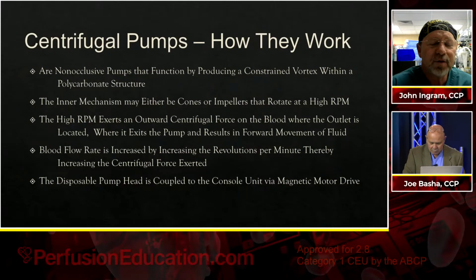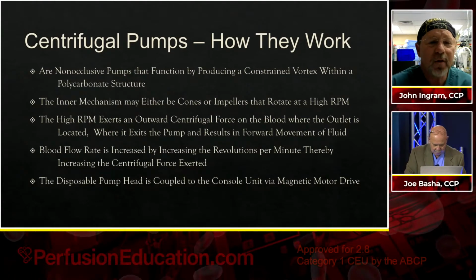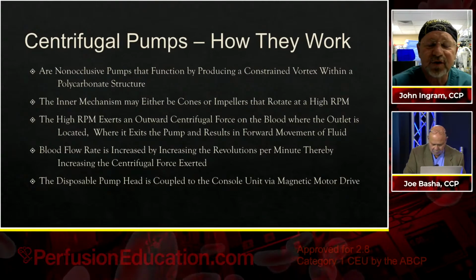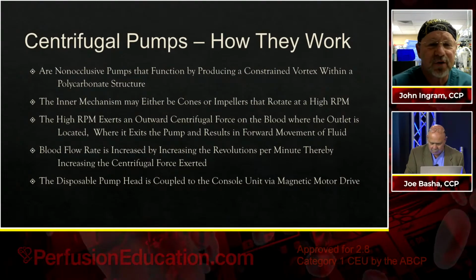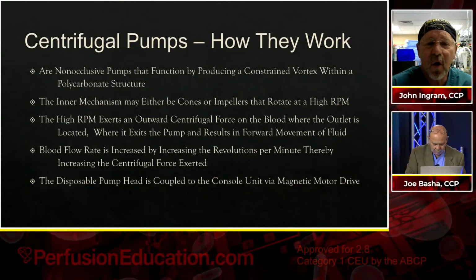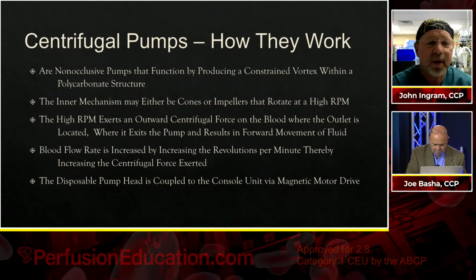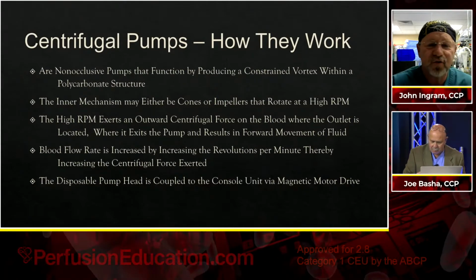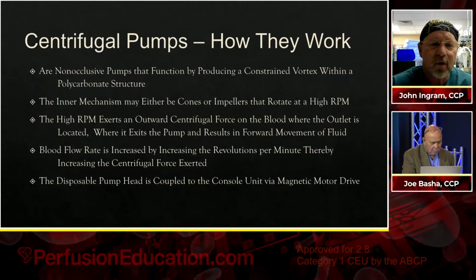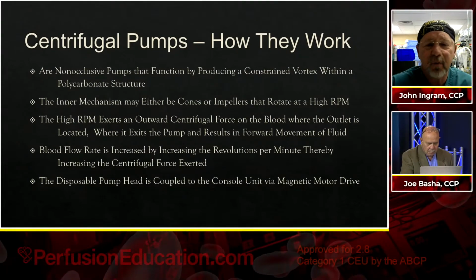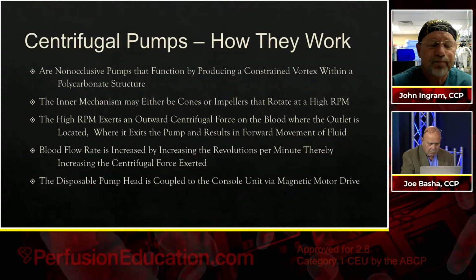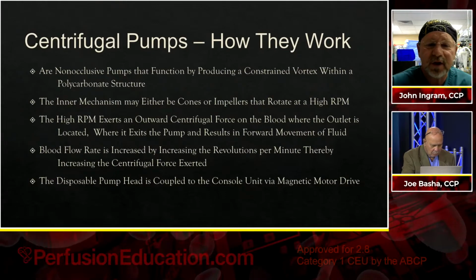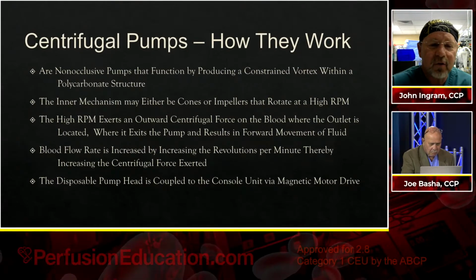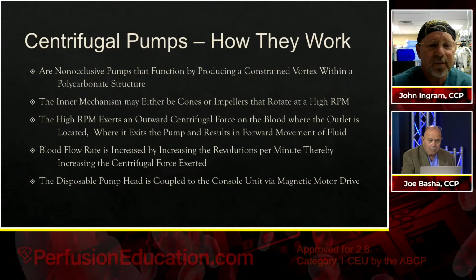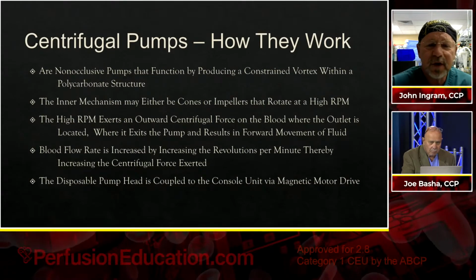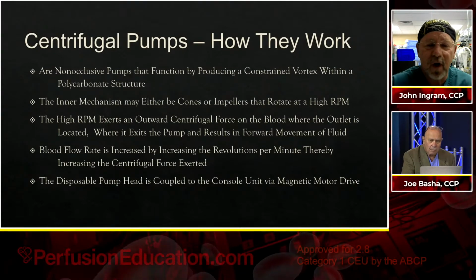Go ahead, Jim. So now, let's talk about centrifugal pumps and how they work. Well, they're a non-occlusive pump, and they function by producing a constrained vortex within a polycarbonate structure. The inner mechanism may either be cones or impellers that rotate at a very high RPM. This high RPM exerts an outward centrifugal force on the blood where the outlet is located, where it then exits the pump and results in a forward movement of the fluid. The blood flow rate is increased by increasing the revolutions per minute, the RPM, thereby increasing the centrifugal force that's exerted on the fluid. The disposable pump head is coupled to the console unit via magnetic motor drive.